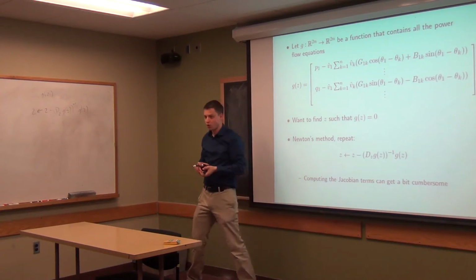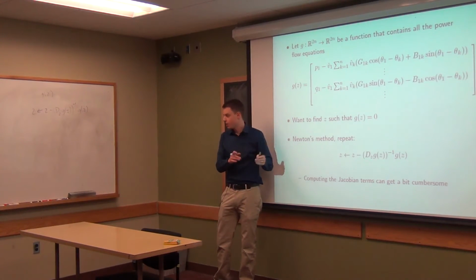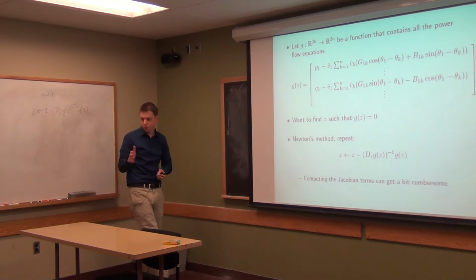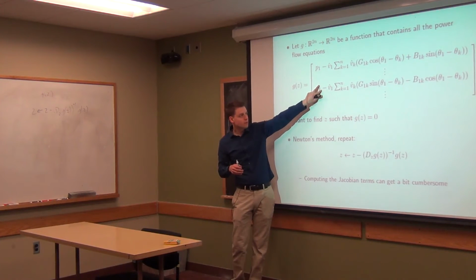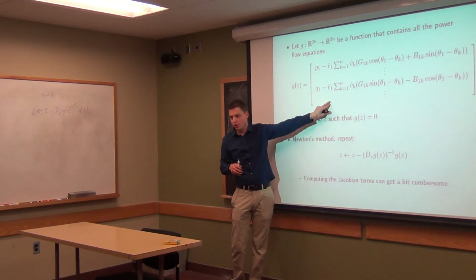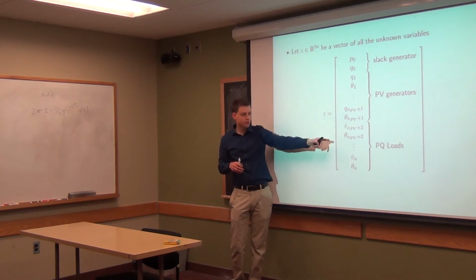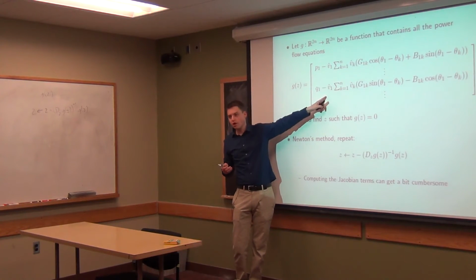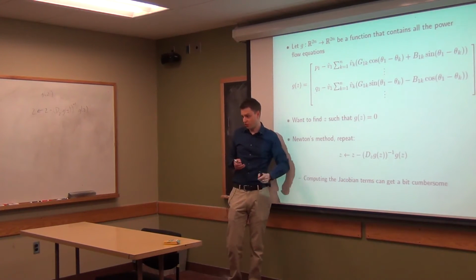Okay, we're actually going to go back to our older form of the vector form. It makes things much, much easier. But let's just think conceptually we can do this. And really, a lot of books describing power flow will do this exactly. And say, okay, now we have 2n equations. We have 2n unknowns, all these variables here. Let's just compute the derivative of every single one of these with respect to every single one of the other things. And those let us compute the Jacobians.